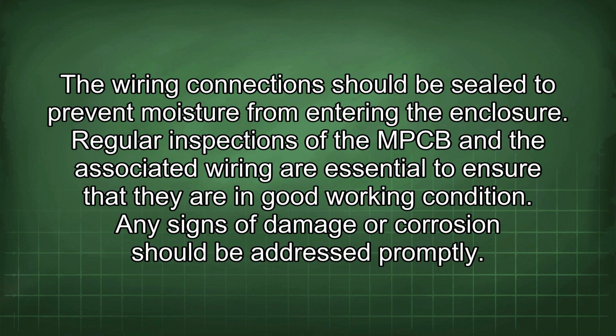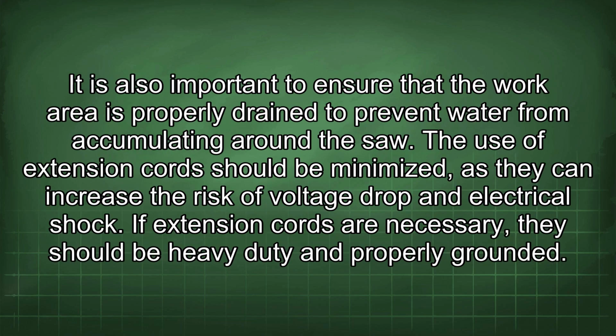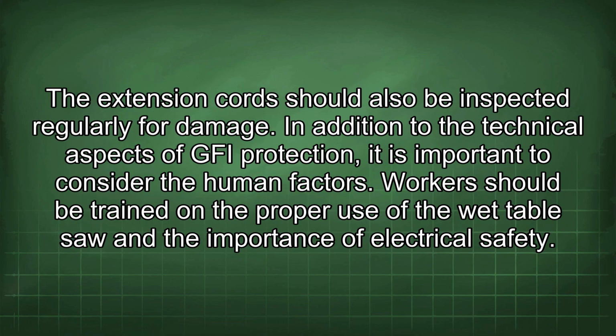Regular inspections of the MPCB and the associated wiring are essential to ensure that they are in good working condition. Any signs of damage or corrosion should be addressed promptly. It is also important to ensure that the work area is properly drained to prevent water from accumulating around the saw. The use of extension cords should be minimized, as they can increase the risk of voltage drop and electrical shock. If extension cords are necessary, they should be heavy-duty and properly grounded. The extension cord should also be inspected regularly for damage.